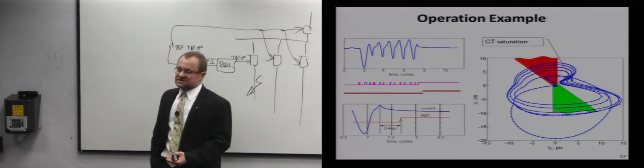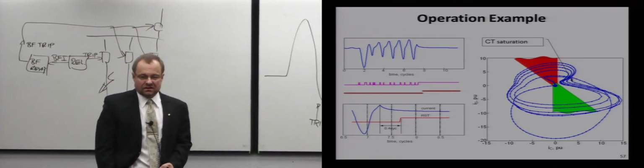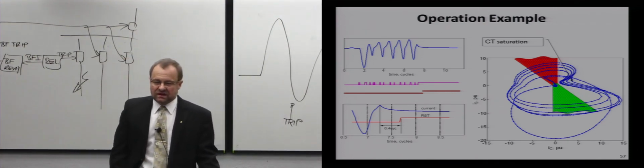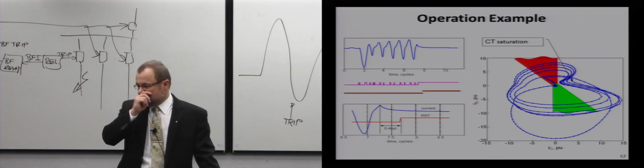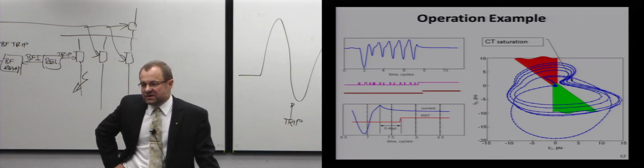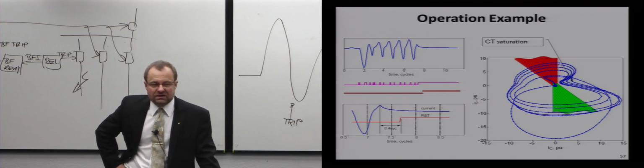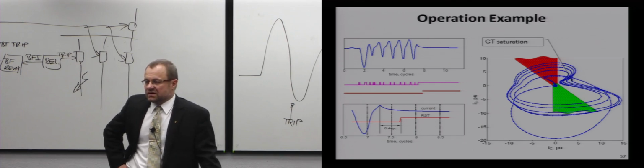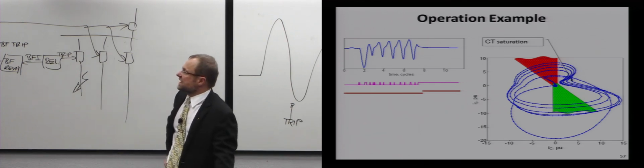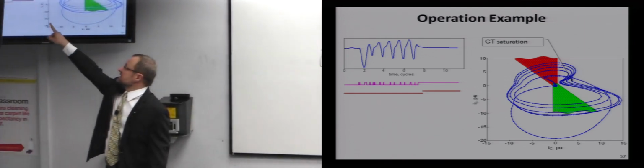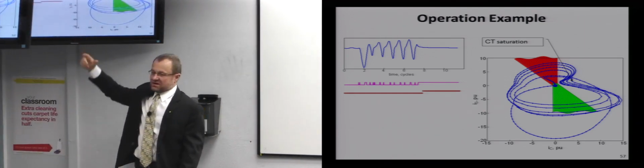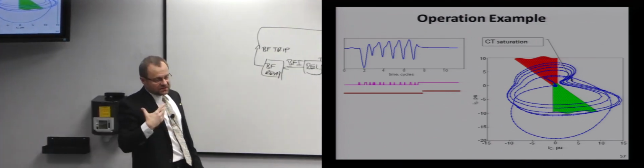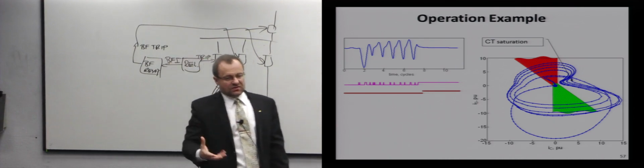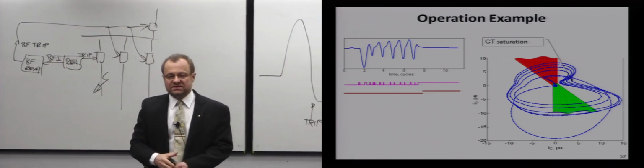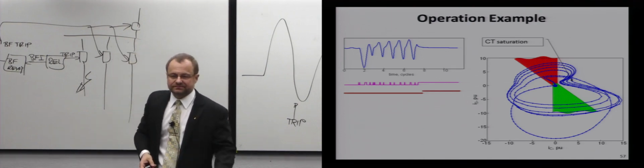Now, does it depend on any specific phasor estimators? I pick those sine, cosine, 1/f of a cycle. Do they have to be accurate? No. Do I have to spend months researching that part? No. It's just a sound heuristic observation that I use to decide whether I am dealing with alternating current, meaning the breaker didn't open, or I am dealing with a current that is not zero, but clearly is a fictitious current that is not coming from a generator that is supplying a fault. It's an artifact of current transformer saturation.